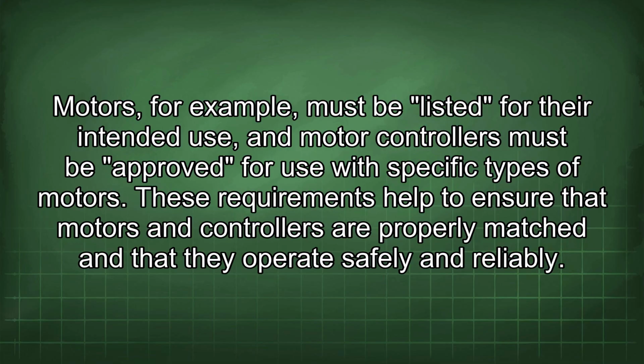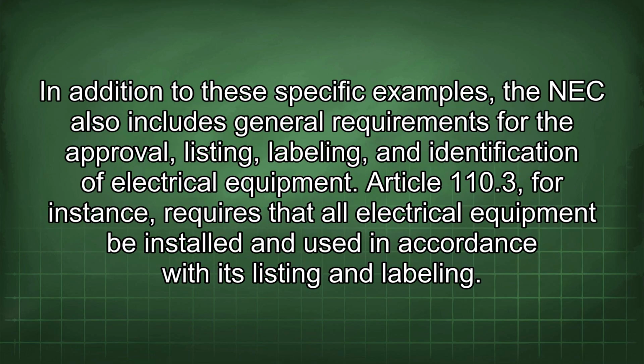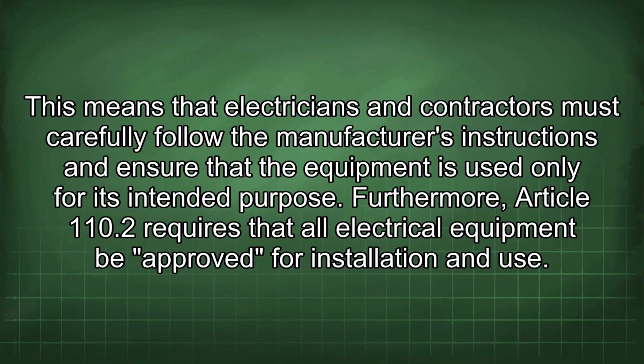In addition to these specific examples, the NEC also includes general requirements for the approval, listing, labeling, and identification of electrical equipment. Article 110.3, for instance, requires that all electrical equipment be installed and used in accordance with its listing and labeling. This means that electricians and contractors must carefully follow the manufacturer's instructions and ensure that the equipment is used only for its intended purpose. Furthermore, Article 110.2 requires that all electrical equipment be approved for installation and use.